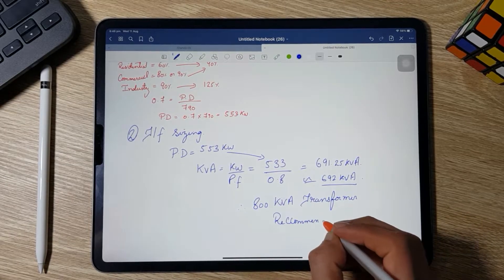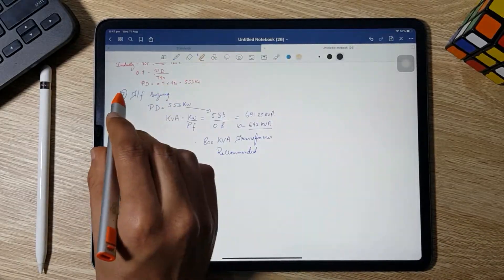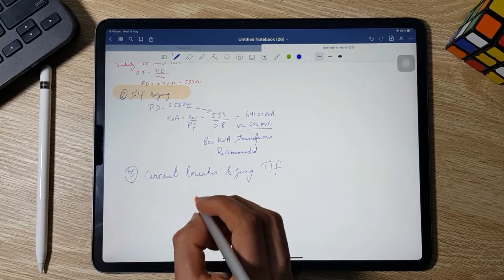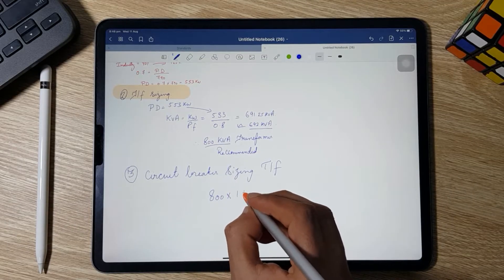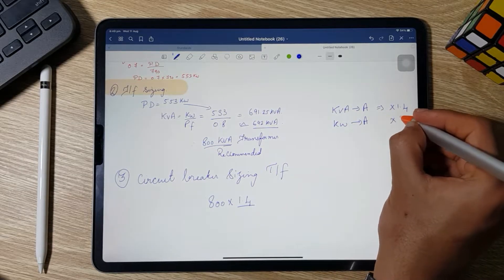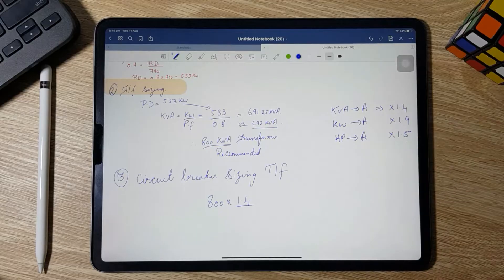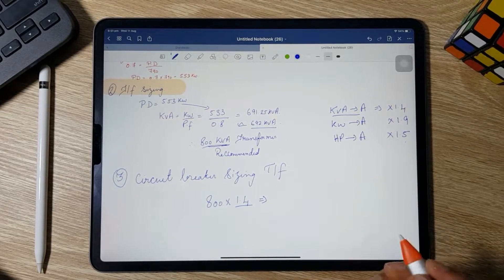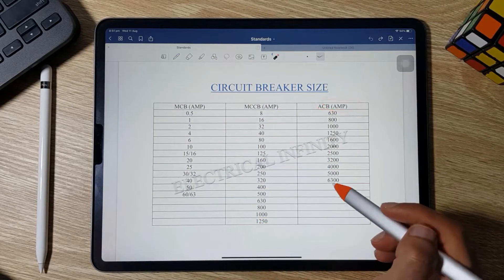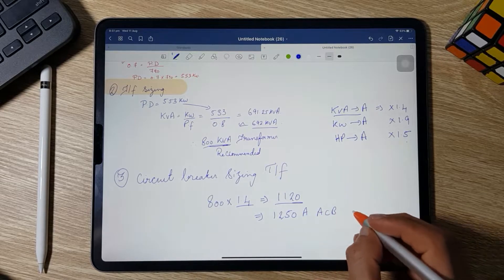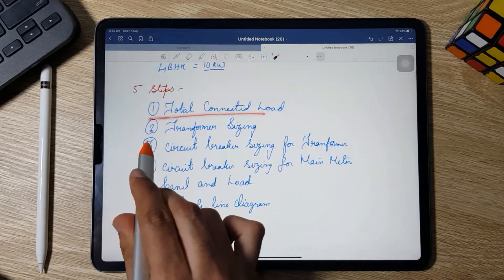Step 3 is circuit breaker sizing for the transformer. The conversion factors are: kVA to ampere — multiply by 1.4; kW to ampere — multiply by 1.9; HP to ampere — multiply by 1.5. So 800 kVA × 1.4 = 1120 A. According to standard sizes, a 1250 A ACB triple pole is recommended for the transformer.